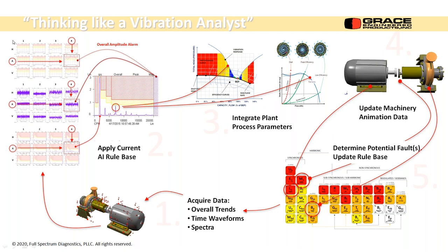So what you'll get is 12 measurements. The top block here are the overall levels, and that's primarily what we're sensing. We're looking for overall levels. We're checking for changes, something to go in alarm. And once that happens, let's say we're in the block here and we get into the alarm range, then we're on demand going to say, hey, we need to capture a time waveform. We need to capture a spectrum. We need to review that and see if there's any alarms in that spectrum.